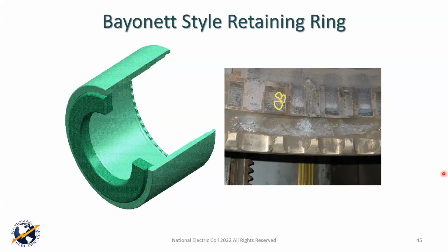The need to do the NDE and the checking of the rings is to a certain extent based on, one, what you've got, two, how you've treated it, and three, where you're at since the last inspection and what condition it was in at the last inspection. Okay? If they're non-magnetic 18-18, if you're taking really good care of it and you're not allowing the thing to see much moisture, even though it is 18-18, I wouldn't be tremendously concerned with it.